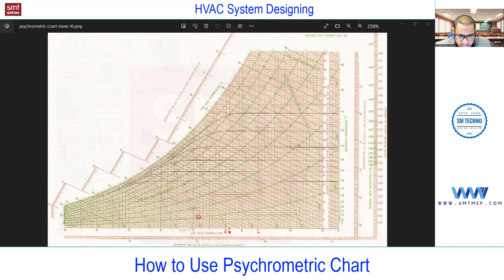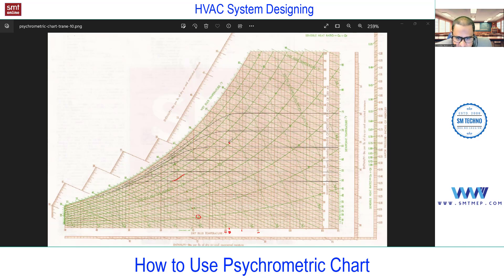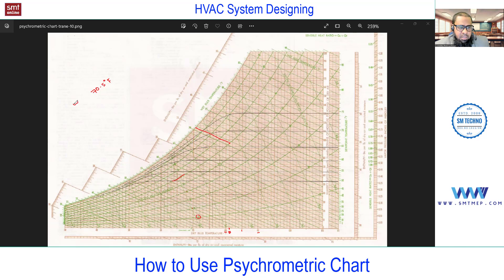On the chart, 60% RH is identified — you can see 10%, 20%, 30%, 40%, 50%, 60%. Going straight up from 81°F dry bulb and intersecting with the 60% RH curved line gives the state point. From that point, drawing a line parallel to the inclined wet bulb lines, I can find the wet bulb temperature — reading the scale gives approximately 70.5°F wet bulb.